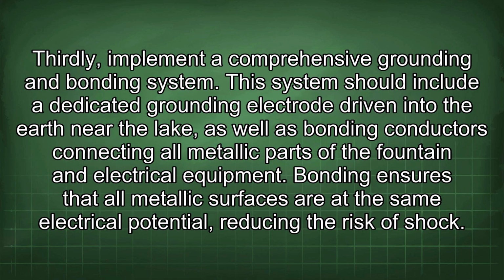Thirdly, implement a comprehensive grounding and bonding system. This system should include a dedicated grounding electrode driven into the earth near the lake, as well as bonding conductors connecting all metallic parts of the fountain and electrical equipment. Bonding ensures that all metallic surfaces are at the same electrical potential, reducing the risk of shock.